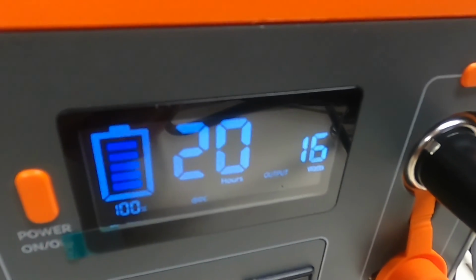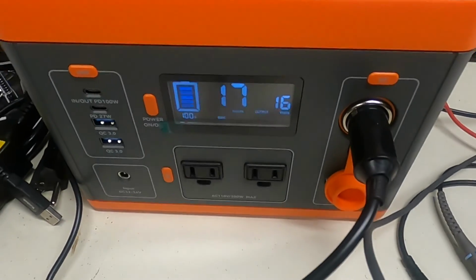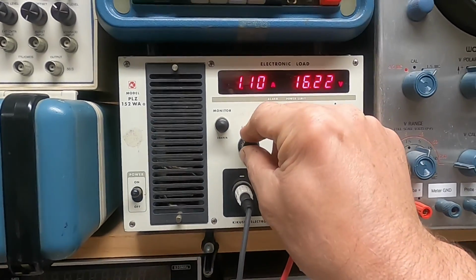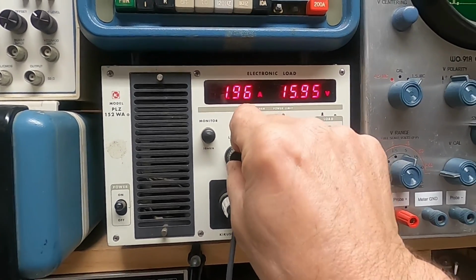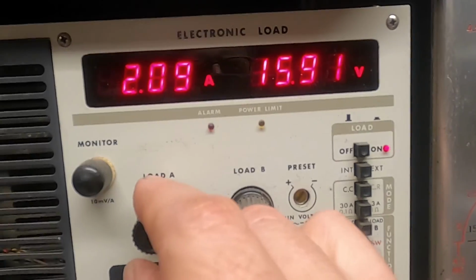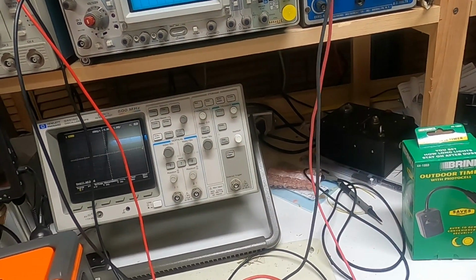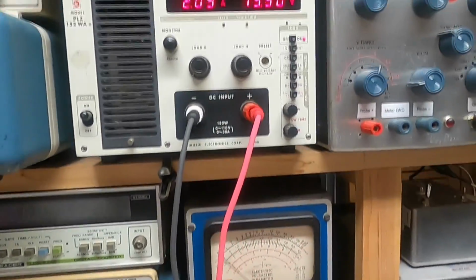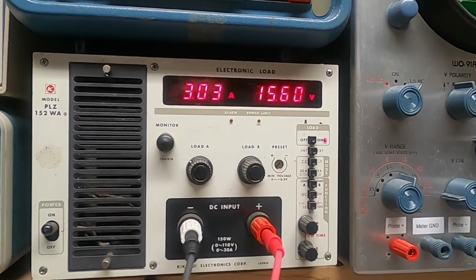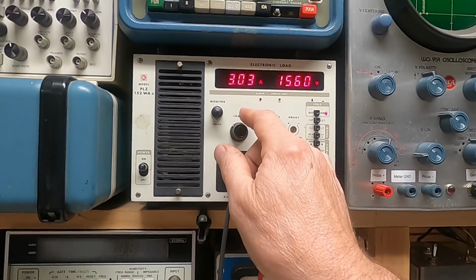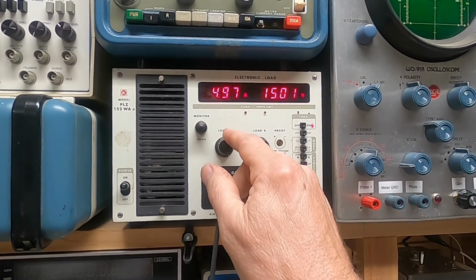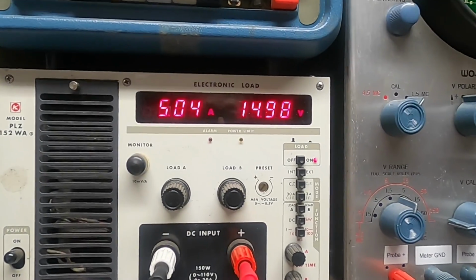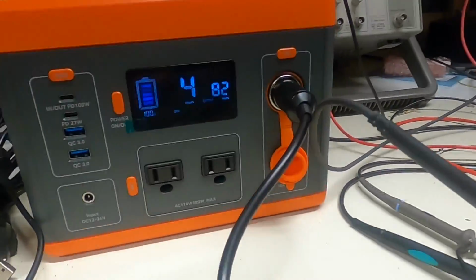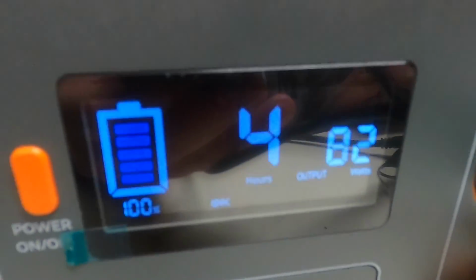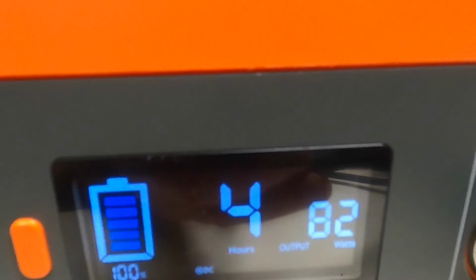There's 16 watts. So now let's try bringing it up to 2 amps. And now you see our voltage is starting to drop a little bit. Just making sure my leads aren't getting warm. Alright, 3 amps. Let's go up to 5 amps. Now our voltage is looking more like it should, if there was an actual load on this. And now we can see our wattage is at 82.